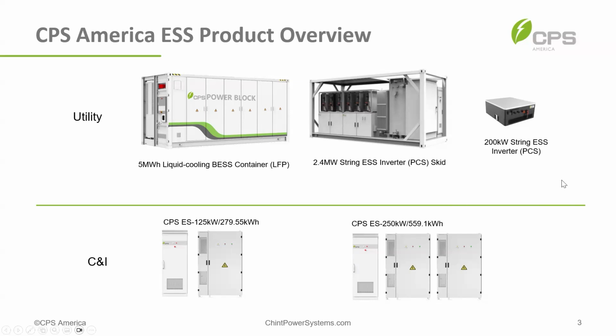The goal being easy installation, quick commissioning, and less downtime in the long run. I did a white paper the other day comparing a central BESS inverter versus our string design. And if you run it out for a 20-year lifespan, you see that if there's one or two instances of failure, you really just need one instance of failure from that central inverter to make it not worth your money versus a string design system.